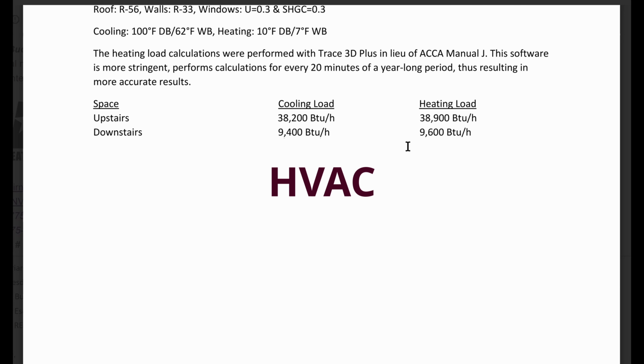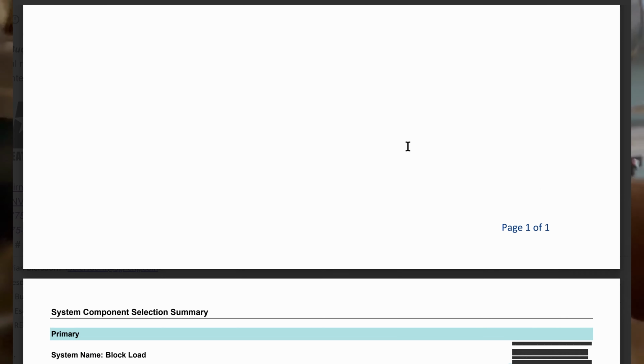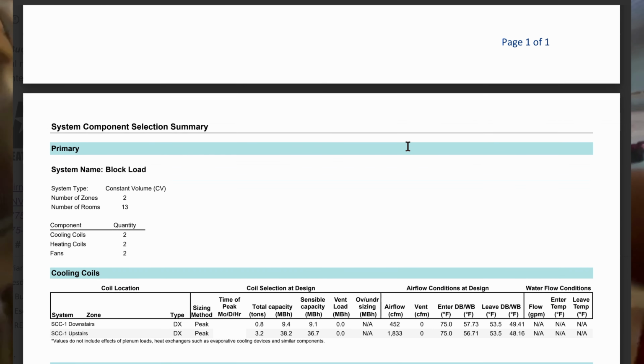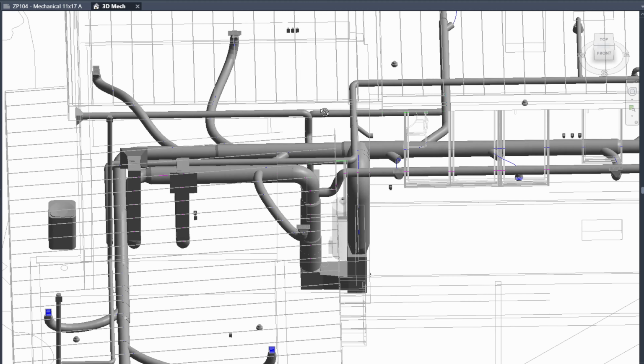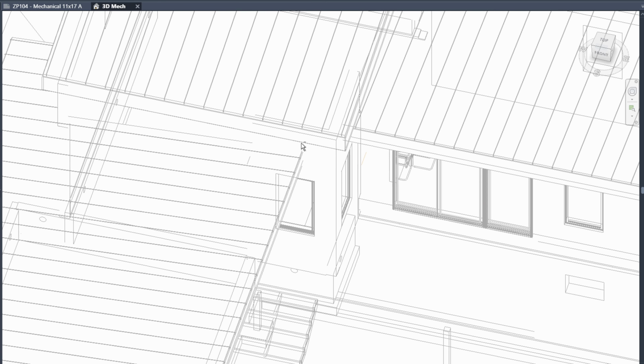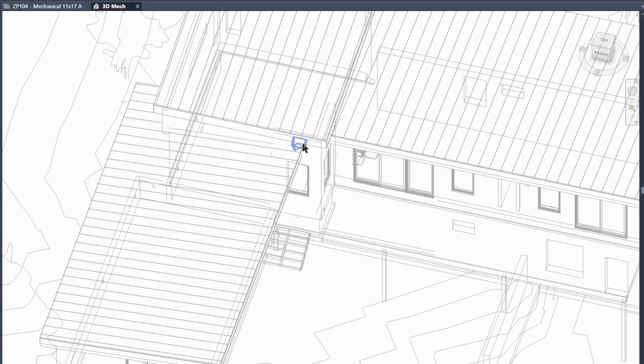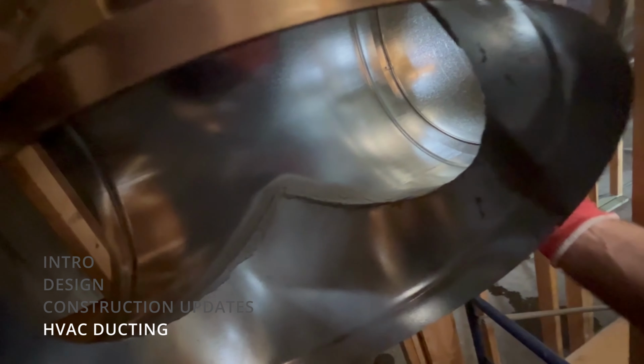I got a third party to do a more detailed load calculation, which indicated a larger system. So I ended up rerunning the duct design and calculations, which upsized the system from a 14-inch at the largest part, the main trunk, up to a 16-inch main trunk.